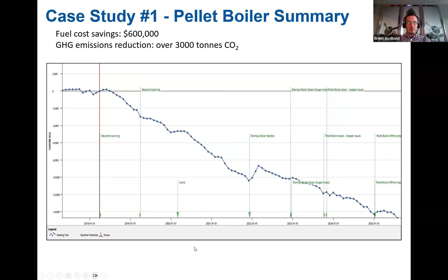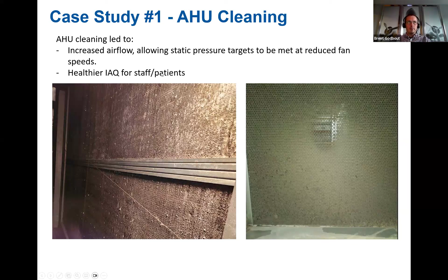These facilities folks also took it upon themselves to clean out, they did a major cleaning of their air handling units. Not always easy to do that, especially in a hospital environment. A lot of the times you can't do them all at once, but they did do that. This was one of the worst ones that they cleaned out. But as a result of that, we increased our airflows, and we were meeting our static pressure set points at reduced fan speeds, which helps with energy. Better for the patients, obviously, and staff.